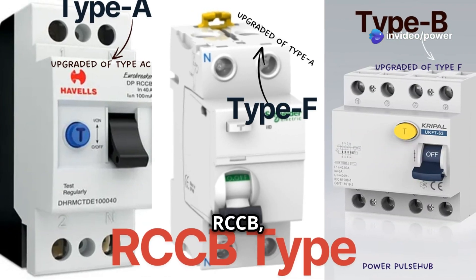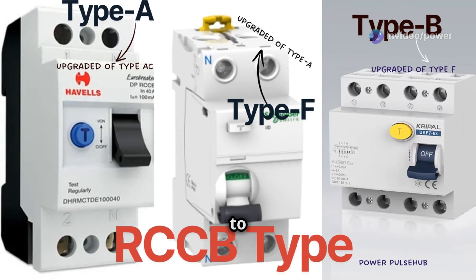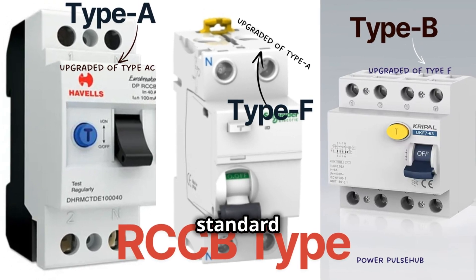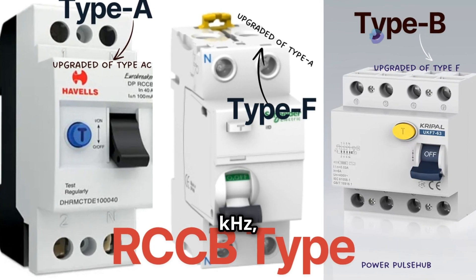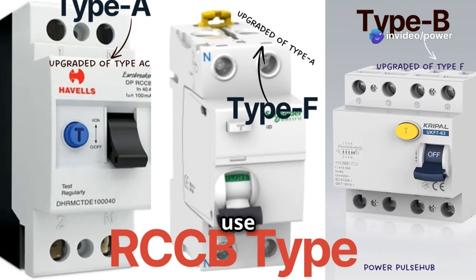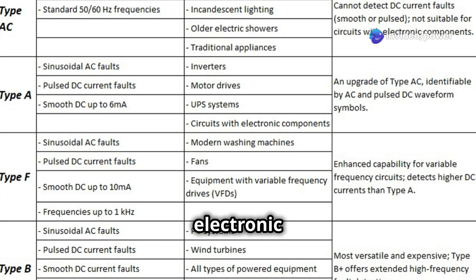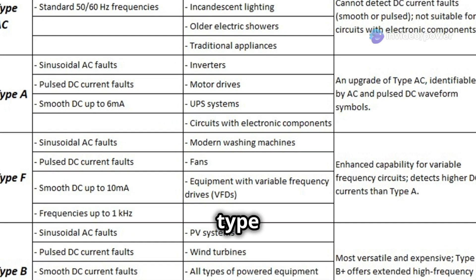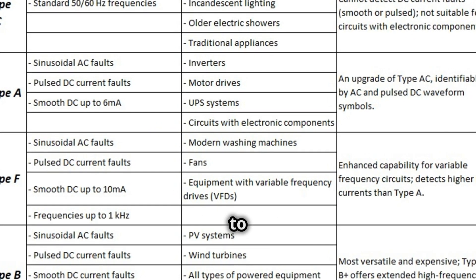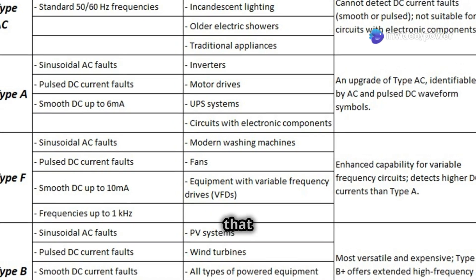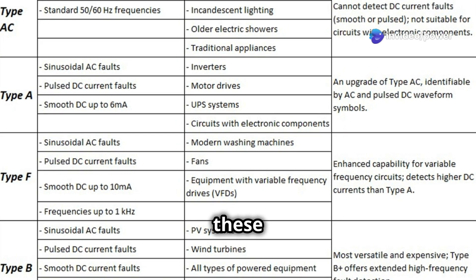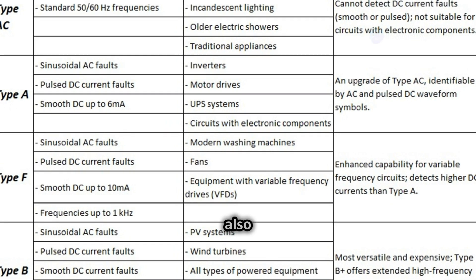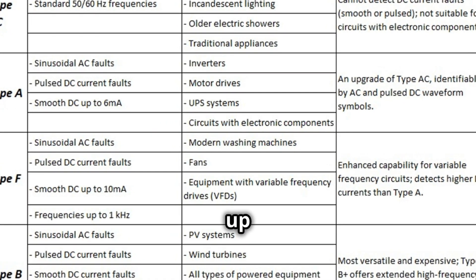The RCCB with Type F covers all the capabilities of Type A and Type AC, but with the added ability to sense frequencies other than the standard 50/60 Hz. It can detect up to 1000 Hz (1 kHz), making it well suited for use with variable frequency drives and other electronic equipment. Use this type of RCCB for applications where you need to protect persons from fault currents in modern washing machines, fans, and other equipment that uses a variable frequency drive.